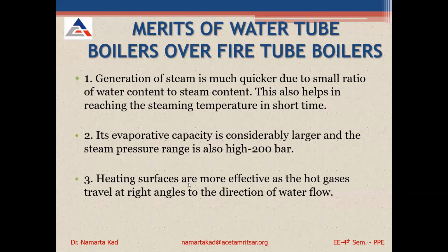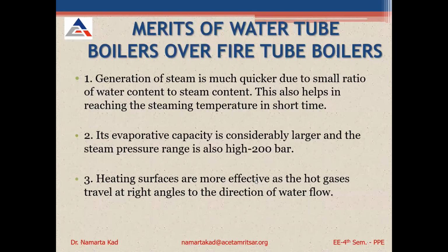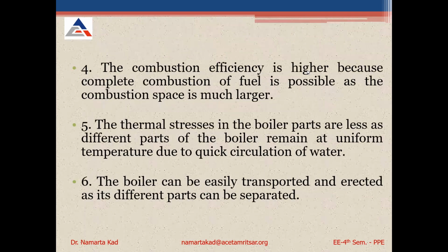Third is heating surfaces are more effective as the hot gases travel at right angles to the direction of water flow. Okay. See here the water flows in this direction and the heat flows over these tubes. So the heating surfaces are more effective. The combustion efficiency is higher because the complete combustion of fuel is possible as the combustion space is much larger. Okay, here the combustion efficiency is high as compared to the fire tube boiler.